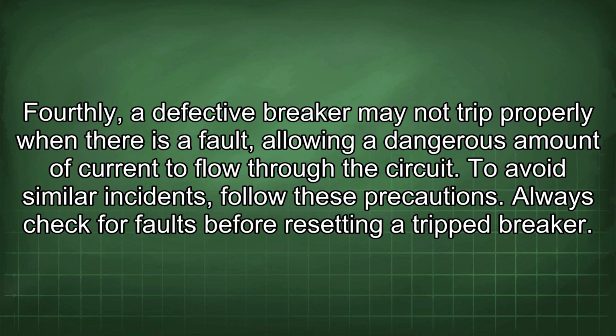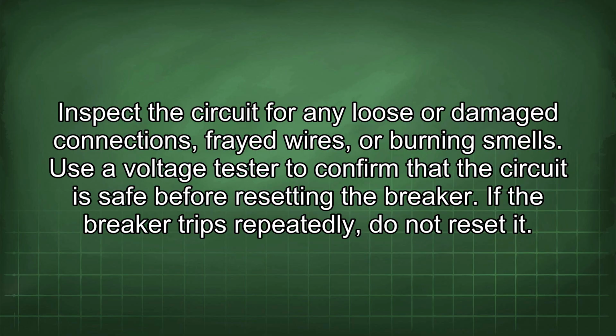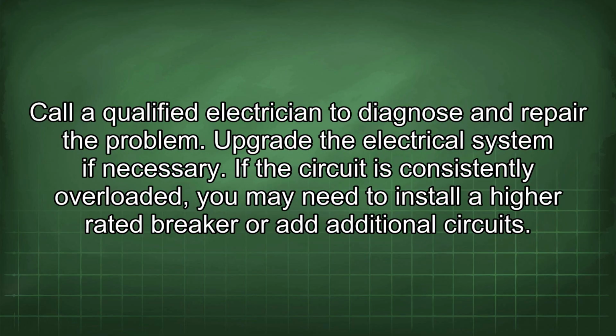Always check for faults before resetting a tripped breaker. Inspect the circuit for any loose or damaged connections, frayed wires, or burning smells. Use a voltage tester to confirm that the circuit is safe before resetting the breaker. If the breaker trips repeatedly, do not reset it. Call a qualified electrician to diagnose and repair the problem.